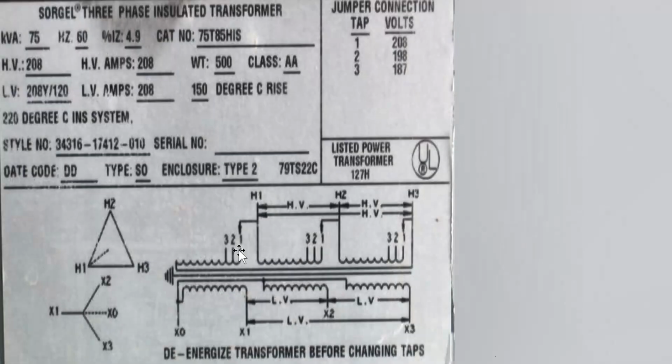If you look at this delta, the way that these are done is you've got H1 right here and H2 right here, okay? Where does that induce on? Okay, that goes onto which coil? I'm sorry, in H3 right here. Well, let's look at the A phase coil. How can you find the A phase? We have a Y on the secondary, so there's neutral and there's X1, so that means that this is our A phase coil, okay? That's our secondary A phase.